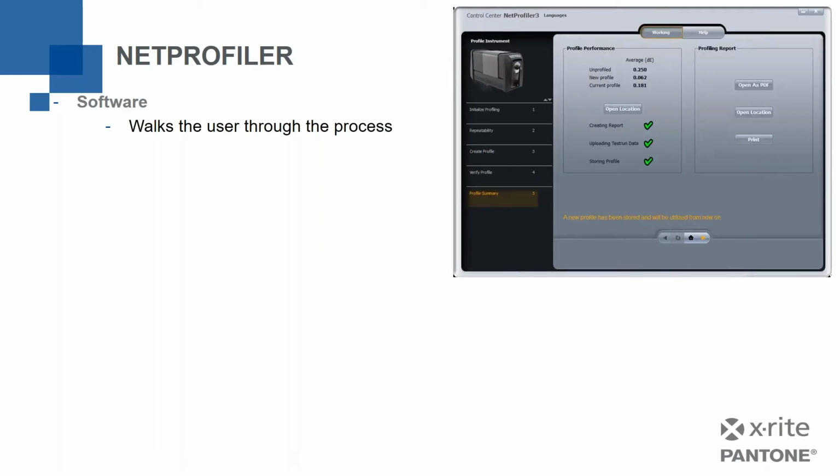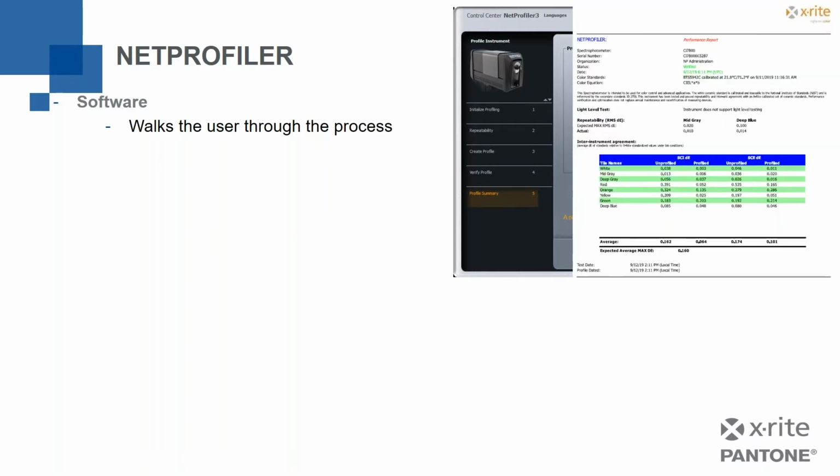And you go through and do measurements and you end up with some measured results for your instrument that you tested. And really quick, I'll show you, you get a performance report. Many customers use this performance report as a means of meeting ISO specifications to show that their instruments are being maintained.